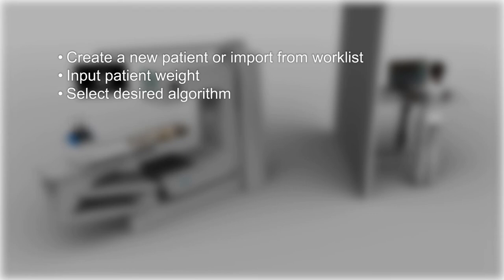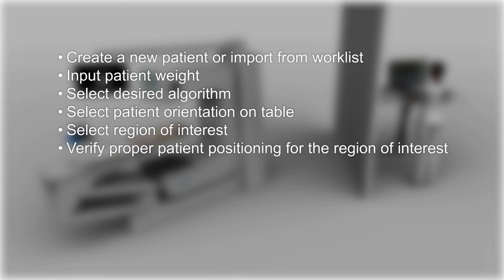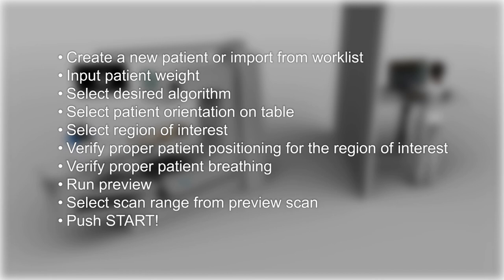Let's review. Create a new patient or import from the worklist. Input the patient weight or size. Select the desired algorithm. Select the patient orientation on the table. Select the region of interest. Verify proper patient positioning for the region of interest. Verify proper patient breathing. Run a preview. Select the scan range from the preview scan and push start. It's that easy.